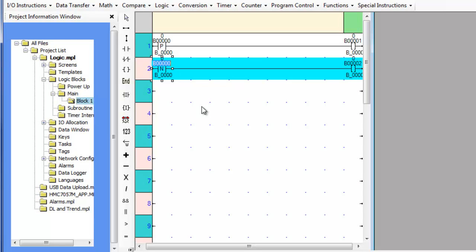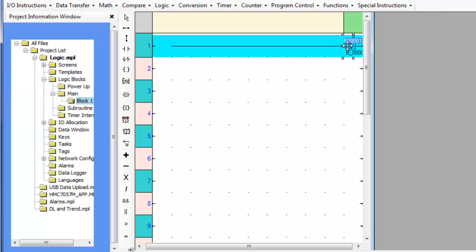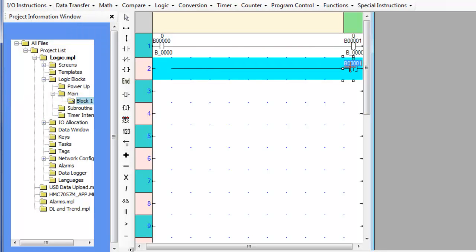Any instructions that follow these conditions will execute when the condition is true. The output coil is an instruction which sets the associated bit when the conditions preceding the coil are true. The invert coil is an instruction that sets the associated bit when the conditions preceding the coil are false. The execution time for these instructions is 1.1 microseconds.